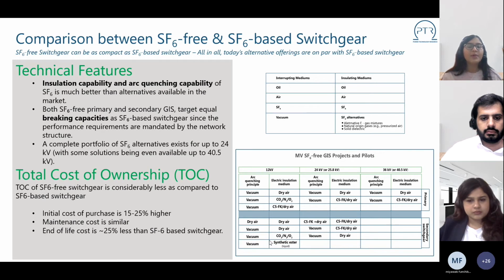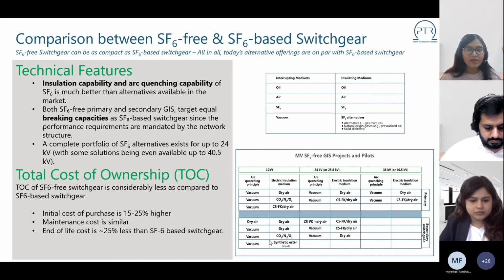Insulation can be solved easily by using SF6 alternate gases that are available, or solid dielectric material, while none of the alternate gases really offers suitable arc extinguishing properties. Those alternate gases do not make the arc extinguishing phenomenon quite worse, and in some cases may help a bit to consolidate the insulation distance of the switching device, but none extinguishes the arc like SF6 does.